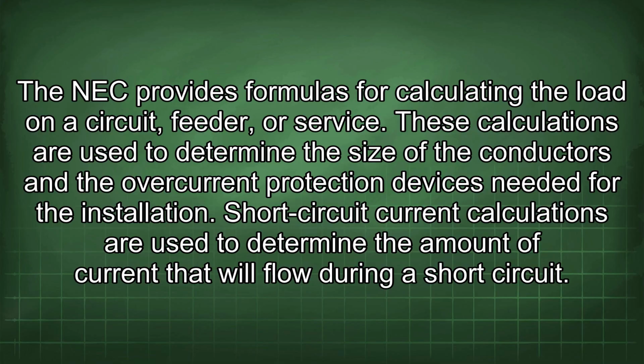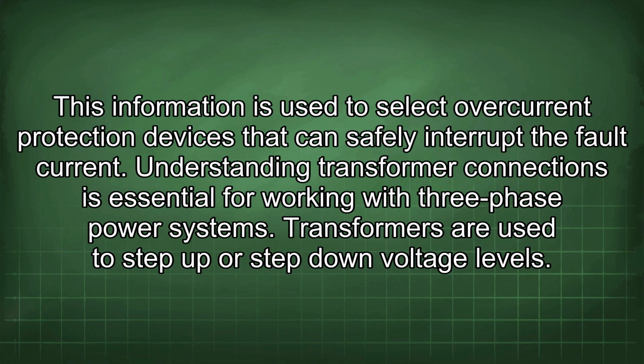Short circuit current calculations are used to determine the amount of current that will flow during a short circuit. This information is used to select overcurrent protection devices that can safely interrupt the fault current.